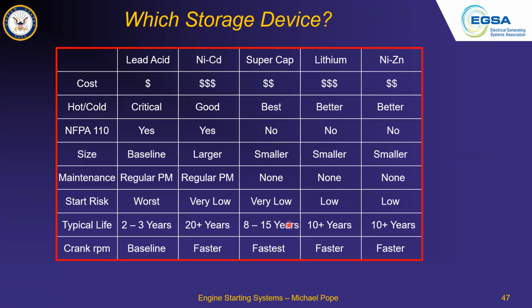Now, since they did, technology has changed, as you can see from the last 3 types of battery on that column there. So they didn't even consider these. Now, the battery manufacturers have gone back to NFPA, and I think EGSA may be a part of that as well, and said, look, there is new technology here, and right now you are not allowing any of these newer types of battery to be used on critical generator sets. And there is good reason why they should be accepted in most cases. So that's the status as I understand it right now on the NFPA 110. But really what they're looking for is just the best reliability you can get.